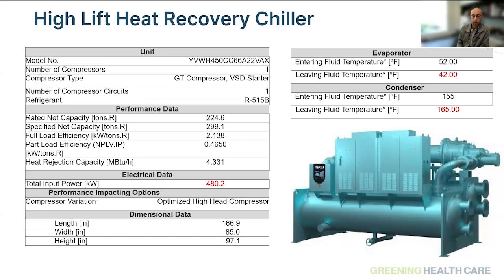It requires different thinking than the typical standard single pass centrifugal or low stage positive displacement machines. These are machines that are more tailored for this type of application, not only in the compressor design, but also in the refrigerant and the refrigerant management side of how the vessels themselves are designed and built.